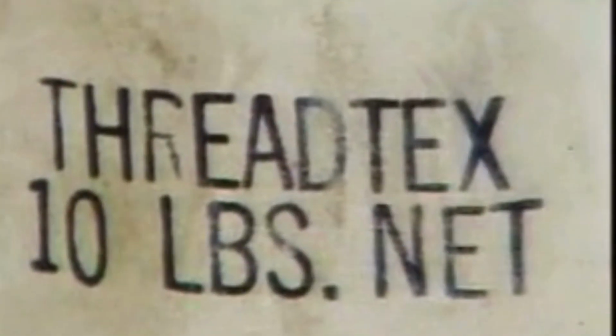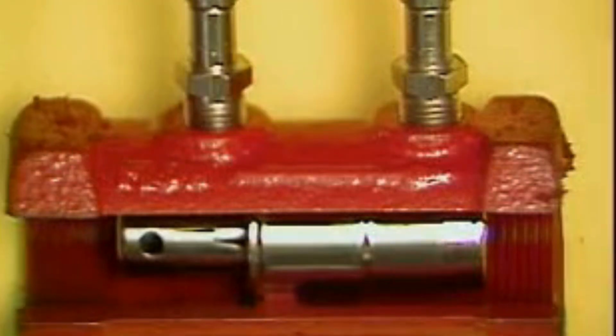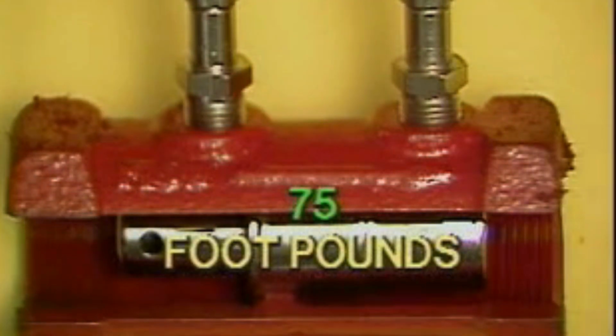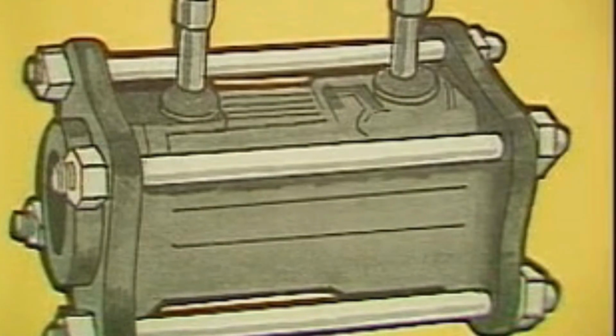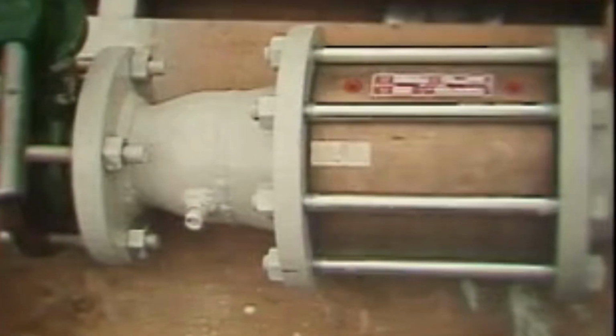And finally, be sure to seal the threaded-in valves with approved pipe compound. Be sure when you use the smaller valves not to torque them down in excess of 75 foot-pounds, because you could damage them. If you've ordered a valve which is the flange-mounted type, be sure and use the studs that are provided by Griswold. They're tested to the proper specifications required for those particular valves. That's really all there is to the installation procedures.